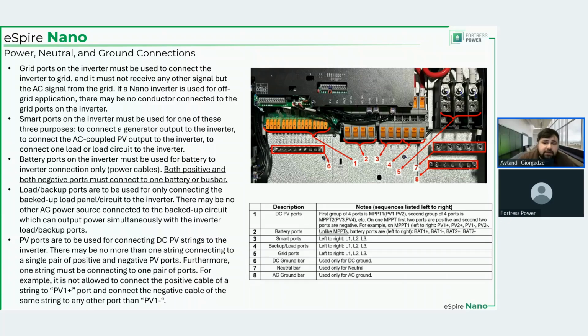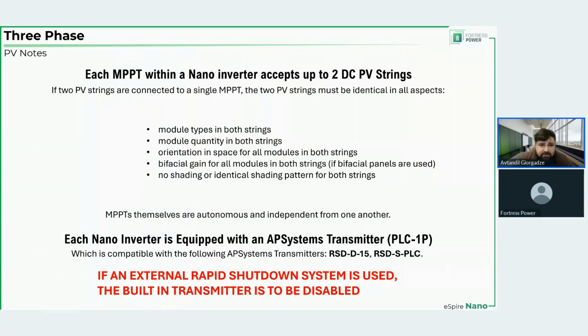There are other notes about the PV that I wanted to share. Multiple times over this webinar, I have mentioned that each MPPT can accept up to 2 PV strings. These are DC coupled PV strings. It is extremely important, it is a rule, it is a must, whatever you want to call it, that those strings are identical in all aspects imaginable. So module types in both strings must be identical. Module quantity in both strings must be identical. Both strings must have identical orientation in space. If there are bifacial PV panels used, all of them must have the identical gain.